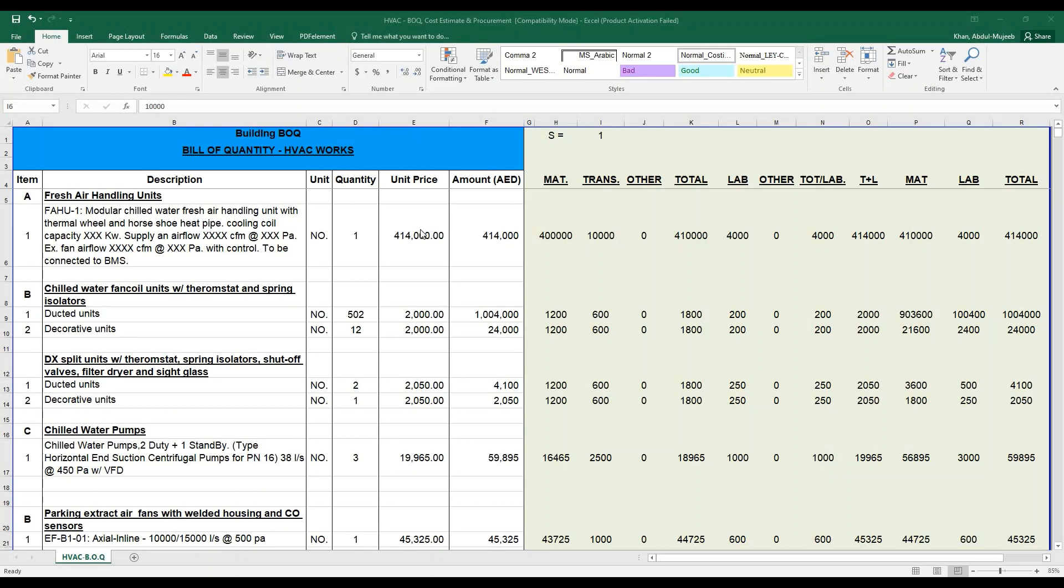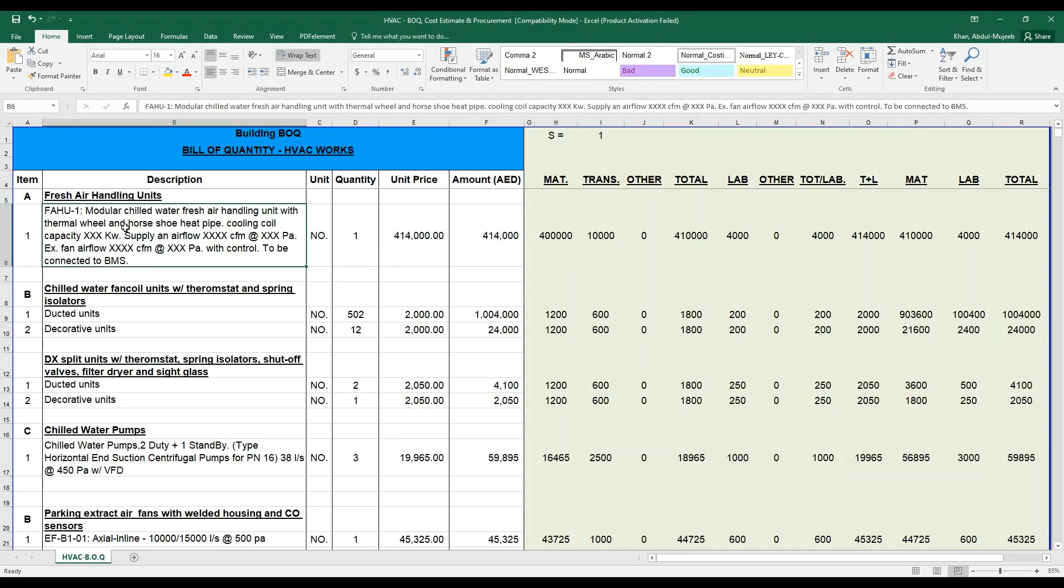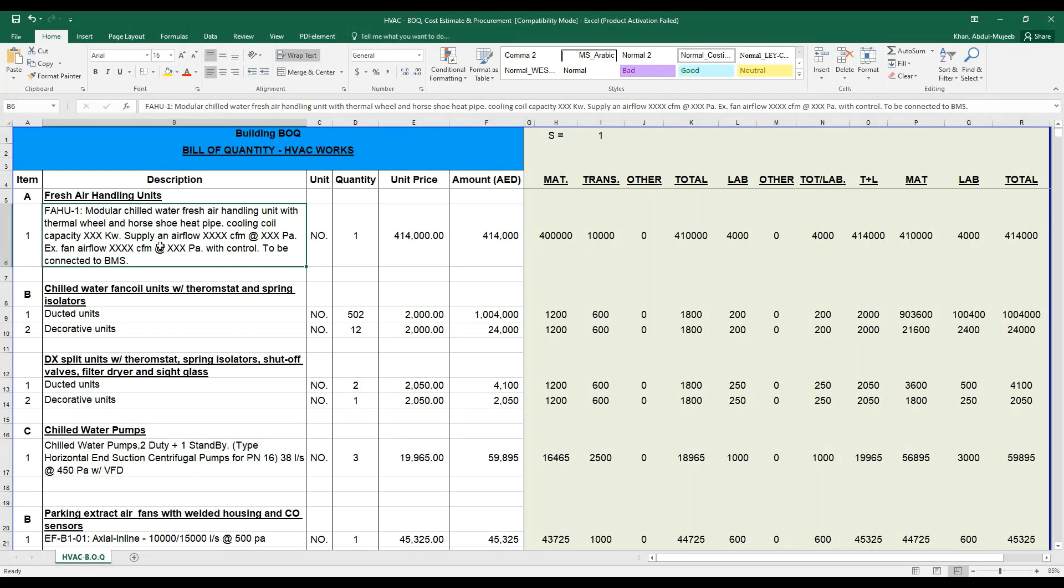the major important parameter required is a fresh air handling unit. We have taken the fresh air handling unit description. The type of the unit will be defined based on your specification, based on your calculated capacity. For example, it is known as a modular chiller fresh air handling unit with thermal wheel, horseshoe, heat pipe, cooling coil capacities, the supply air flow, the static pressure, the external fan air flow, the static pressure with controls to be connected to the BMS.